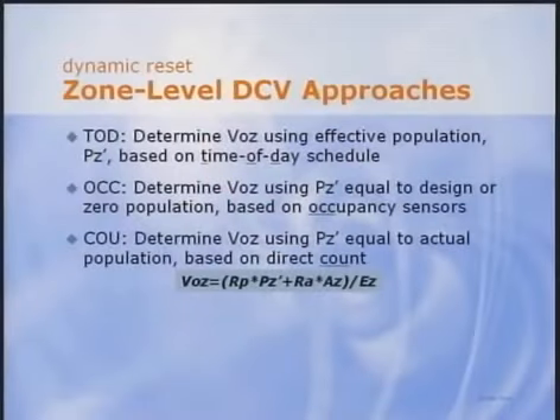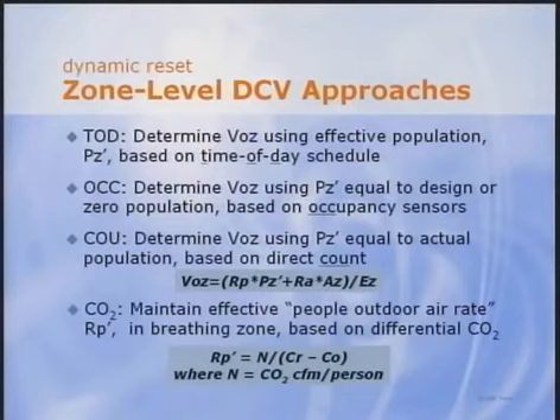But as an alternative to estimating population, many designers want to use CO2 sensors to reset zone outdoor airflow. This approach works because, as the steady-state equation shows, the current per-person outdoor airflow rate in a zone is inversely proportional to the difference between indoor and outdoor CO2 level. Therefore, differential CO2 can be sensed, and a controller can adjust zone outdoor airflow or damper position to change the effective ventilation rate per person. This approach has been widely used in the past and will probably continue to be popular. So if a designer wants to use zone-level demand-controlled ventilation to respond to variations in population, Standard 62 allows it. We covered this topic in a 2005 broadcast, as well as a newsletter and a couple of journal articles if you want more details. But what about dynamic reset based on variations in efficiency?